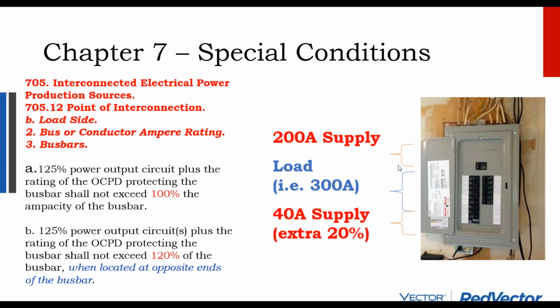But the only thing you really have to consider is if you're plugging solar into the load side of the panel, where you could have 200 amps of power coming in from the main on 300 amps of breakers, and then your additional amperage coming in from solar, that could allow you to pull more than the service panel's rating through it. If you have 300 amps of breakers on and you have your solar array and your main, you could pull 300 amps of load into a 200 amp breaker.